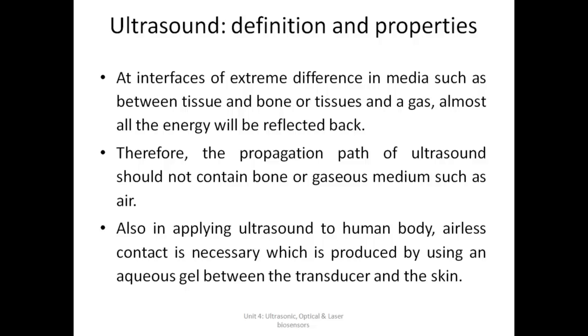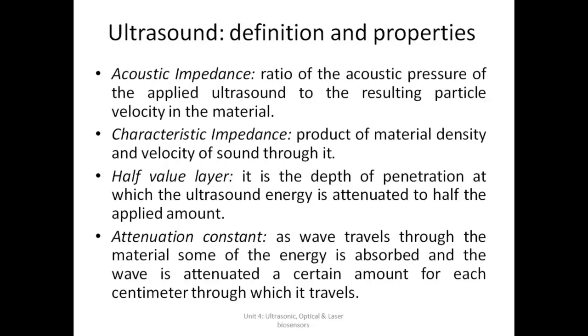That is important, because if there is air in between, then air and your skin have a very vast difference in density. So the ultrasound wave will not have proper propagation if there is air in between. So to have an airless contact, that aqueous gel is used between the transducer and the skin.